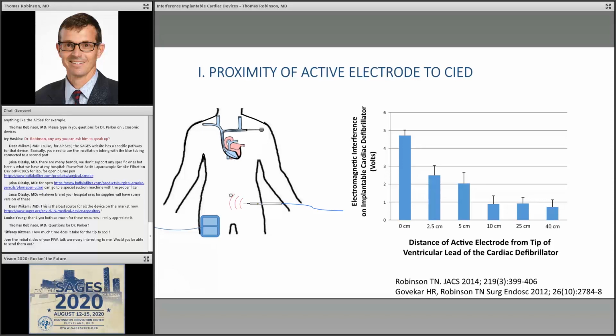And when you're right over the tip of it at 0 centimeters, you cause the most electromagnetic interference that we read on an oscilloscope coming off the lead here. As you get further away, it seemed to plateau once you get down to 10 centimeters. So the rule of thumb that you see in these guideline statements, once you're below the umbilicus, is about, in an adult, 10 centimeters away from the tip of the cardiac implanted device.